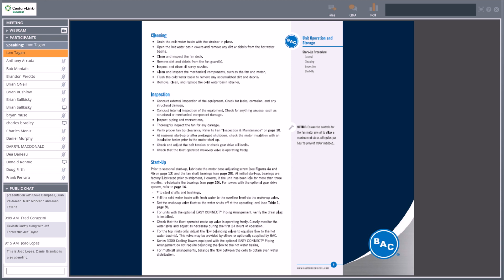So again, very tough to read, but it talks about cleaning the cooling tower. And these 3 items here, the cleaning of it, the inspection, the startup, most of the projects you will be working on or that you're taking over, the contractor's already done this. The cleaning of it is obviously after the cooling tower ships, gets rigged, and they start getting flushed out and things like that. You just want to keep the debris from accumulating, any of the dirt that gets pulled in. Want to keep it clean.